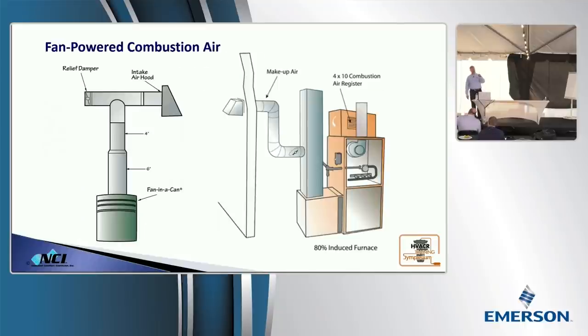And now we get to the fan power. There are going to be situations where the passive won't work, and you need to bring in a fan. For boilers, bring in fan-powered combustion air that's interlocked with the equipment. When it kicks on, the fan in the can kicks on, brings air from the outside in, and pressurizes that space. If you've got a furnace, you can actually use an intake. Field Controls makes a makeup air system that works great, brings the air in every time the furnace runs.